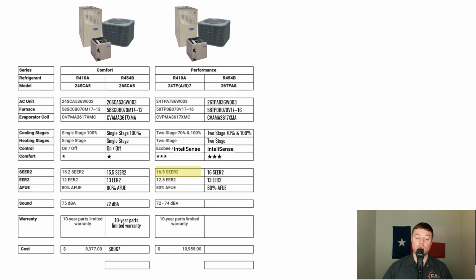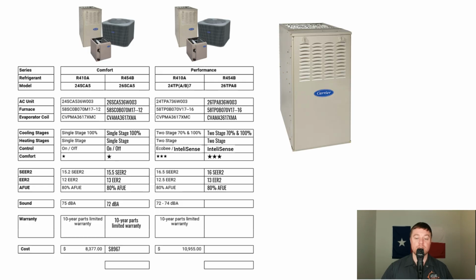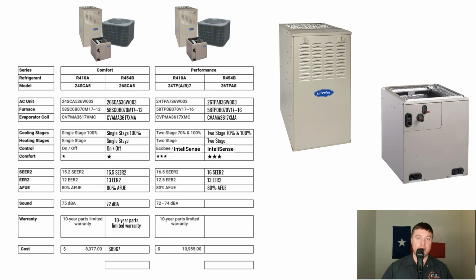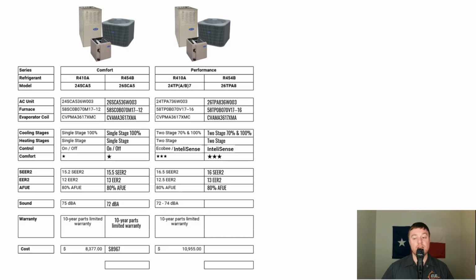You can see that the old equipment was pulling 16.5 SEER2, and the new equipment actually went down some to 16 SEER2. And the EER2 was at 12.5, and for the new equipment it slightly went up to 13 EER2. And the furnaces are identical, so nothing changed there. Now I do want to point out here, I am trying to keep everything apples to apples, and if you wanted a higher SEER rated system, all you would have to do is change out the furnace and the evaporator coil to a more efficient matchup. And if we did that, we could probably squeeze out around 17 SEER out of either one of these systems.